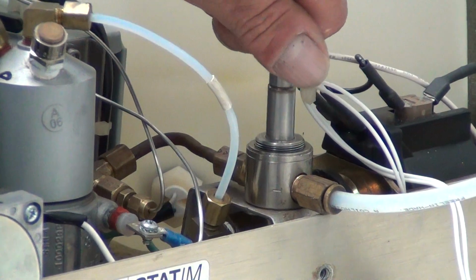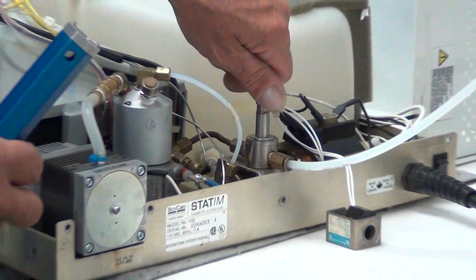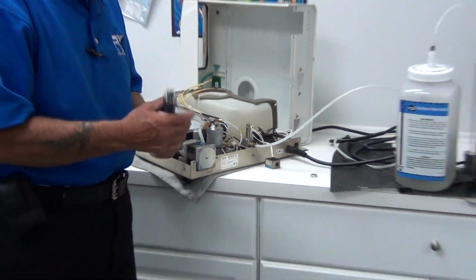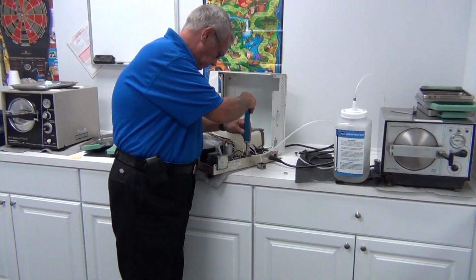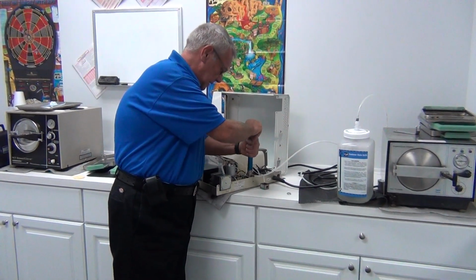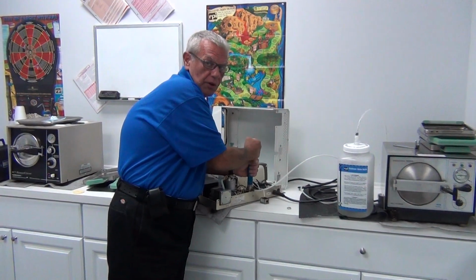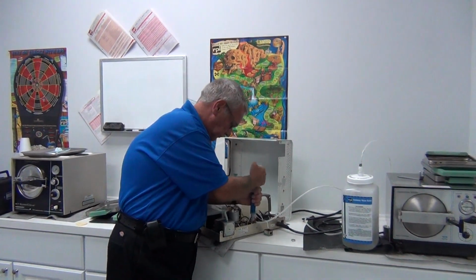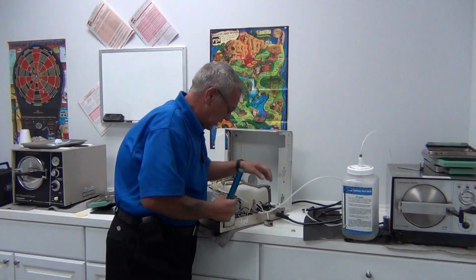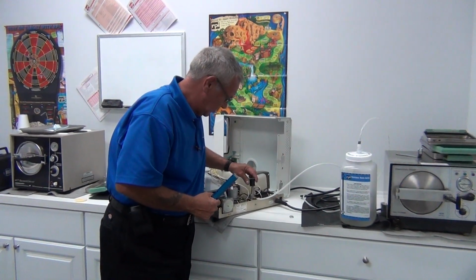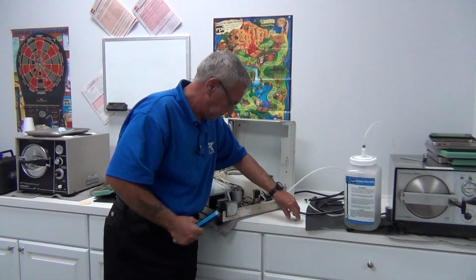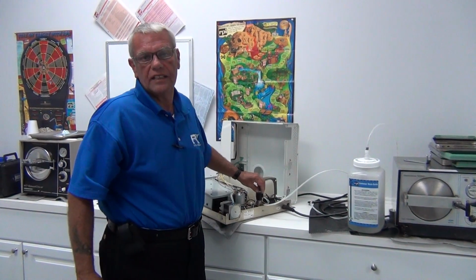Now, while I'm reassembling the solenoid, one word about Statim sterilizers. They must use distilled water. And it must be steam distilled water. The machine will fail immediately, and it will say H2O on the LED readout.